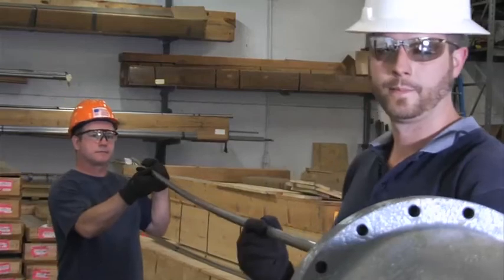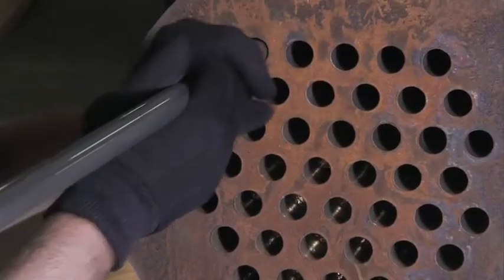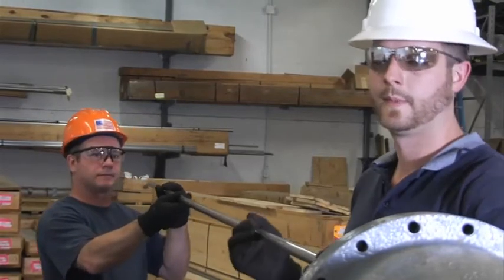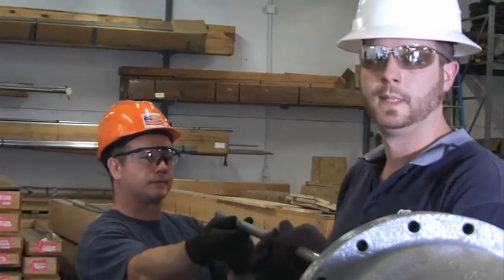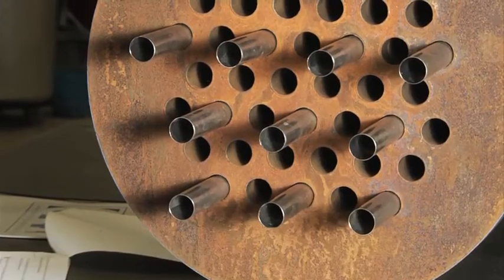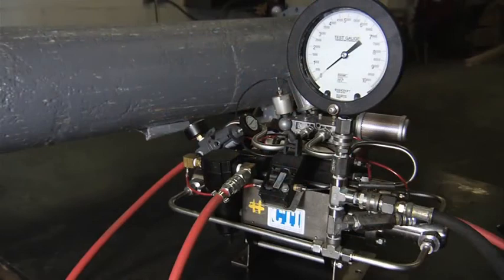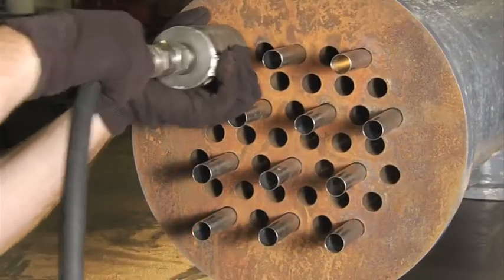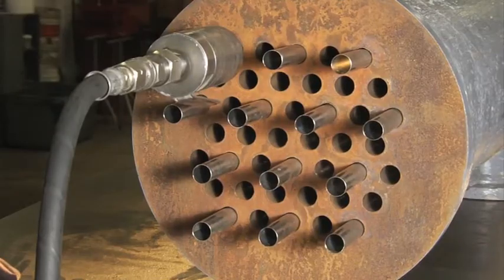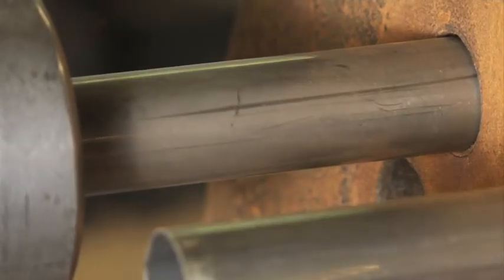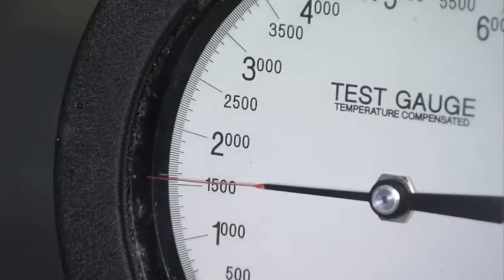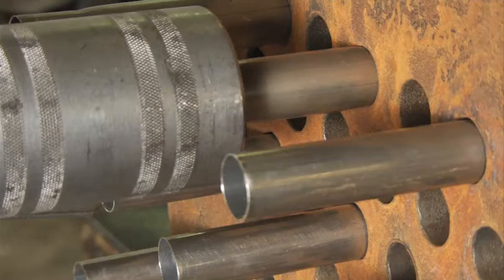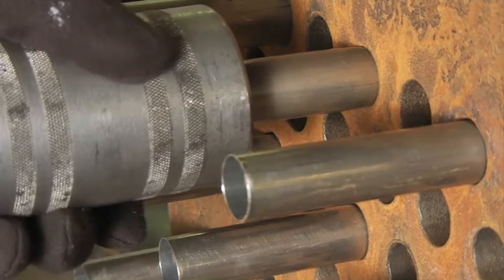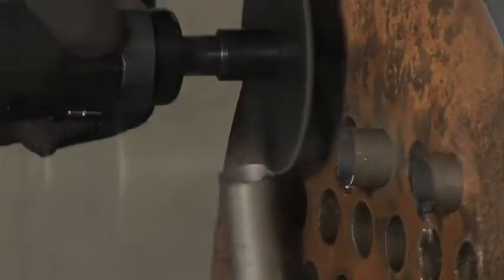CTI has also developed a full-length tube liner for those heat exchangers with tubes suffering full-length problems. Once the tube IDs have been thoroughly cleaned, thin-walled alloy liners are installed into the damaged tubes. A sealing chuck that is connected to the CTI hydraulic liner pump is attached to one end, while a bleed chuck is attached to the opposite end. The liner is filled with water, the air released, and the pump is engaged. When the expansion process is completed, the pressure is allowed to dwell and the chucks removed. Liner ends are cut and trimmed flush to the tube sheet, then roller expanded at each end, completing the repair.